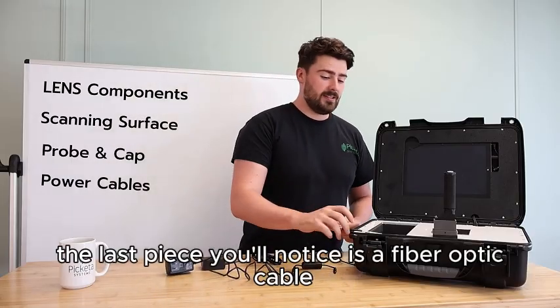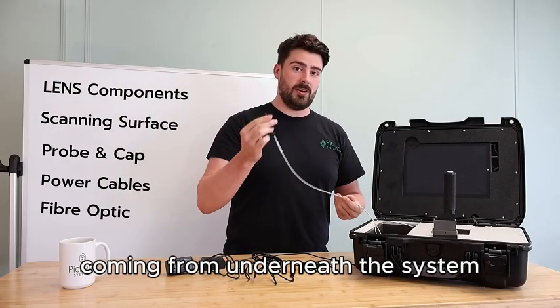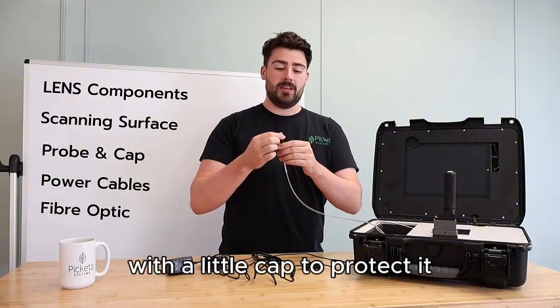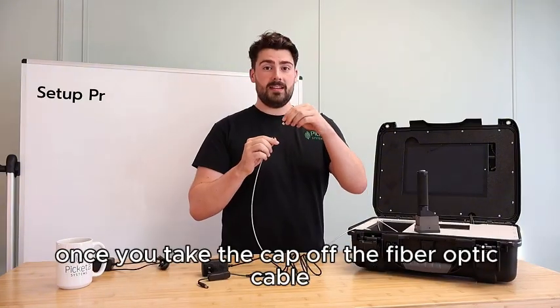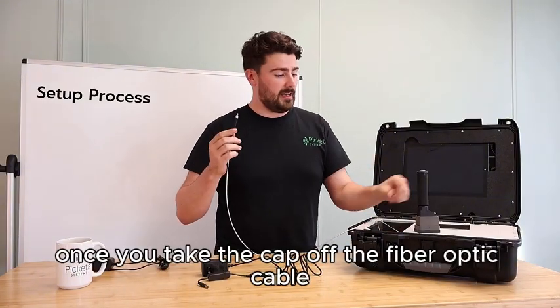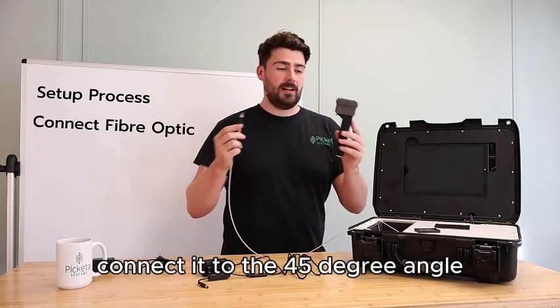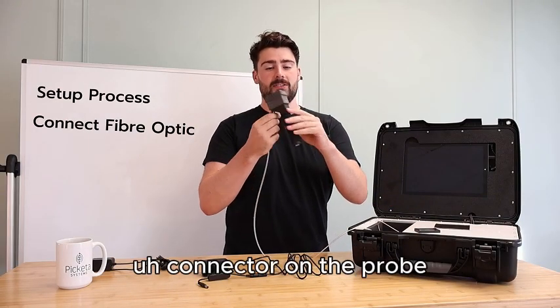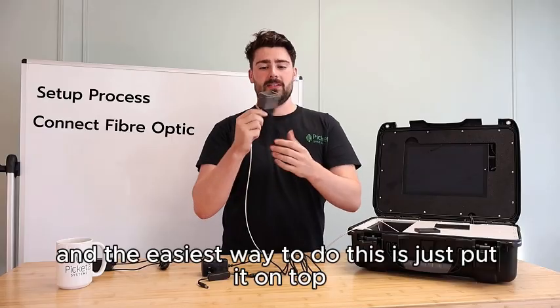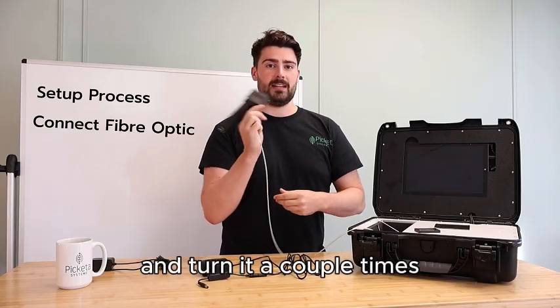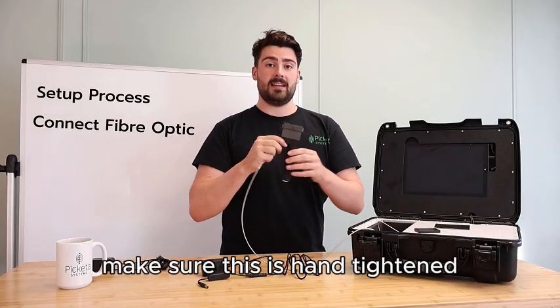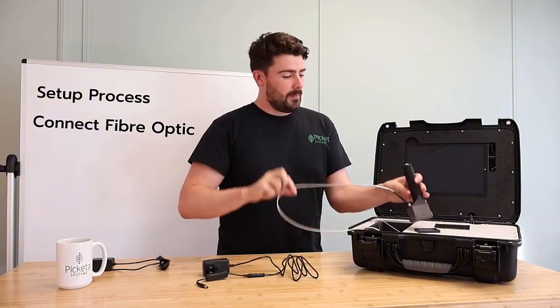The last piece you'll notice is a fiber optic cable coming from underneath the system with a little cap to protect it. Once you take the cap off the fiber optic cable, connect it to the 45-degree angle connector on the probe. And the easiest way to do this is just put it on top and turn it a couple times. Make sure this is hand tightened before you start scanning.